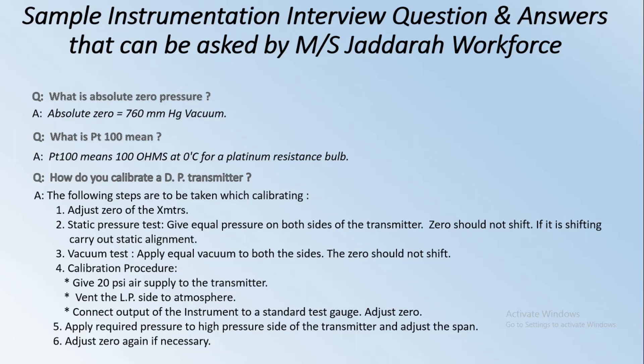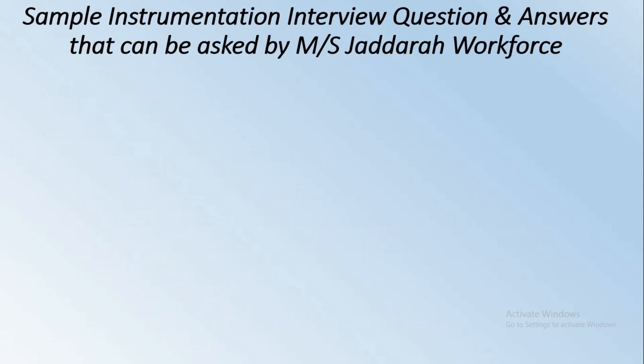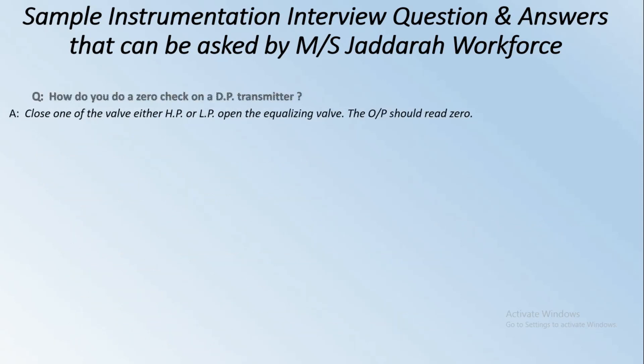Calibration procedure: give 20 PSI air supply to the transmitter with the LP side open to atmosphere. Connect the output of the instrument to a standard test gauge. Adjust zero, apply the required pressure to the high-pressure side of the transmitter and adjust the span. Adjust zero again if necessary.